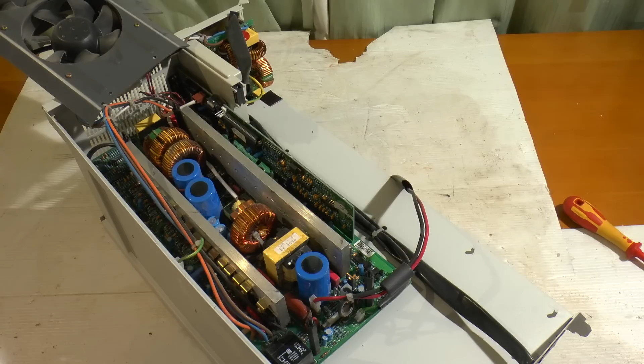What you notice on this one compared to the APC is something missing. There's no big transformer in this. It's not on the other side, that's where the batteries go. It'll take 6 of the 7.2 amp hour batteries as you saw earlier on. So it's a slightly higher voltage system, but there is no big mains frequency transformers in here. What we do have is a pair of transformers here, and these capacitors are rated at 330 microfarads at 400 volts. So there's a clue as to how this works.